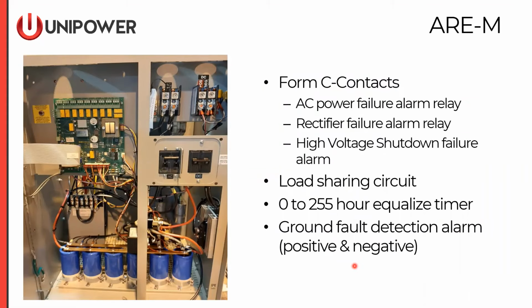So here we're looking inside the ARE-M charger with the door open. On the left, top left quadrant there, we see the alarm interface. This alarm interface, the one shown here, actually is the all alarms interface. There's a standard interface that only includes the 3 relay outputs that we see on the right. Standard relays are high voltage shutdown, AC fail, and rectifier fail. The all alarms relay extends those 3 standards to include summary alarm relay, no charge alarm relay output, low voltage alarm, ground fault positive, and ground fault negative relay outputs.